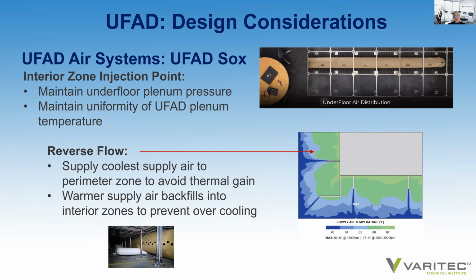Using fabric duct in those days, you could actually bring the supply air to the perimeter, where the coolest air is available to the area which has the greatest load. And then you allow that warmer air gained through thermal decay to backfill into the interior zones, which is more than adequate, because in this way you overcome the overcooling on the interior zones. And this design is more conducive to a successful UFAD layout.